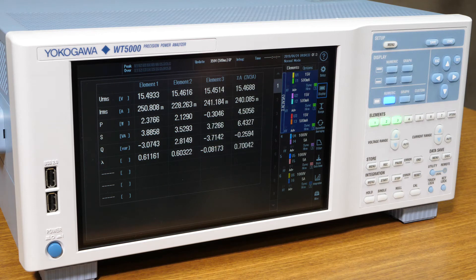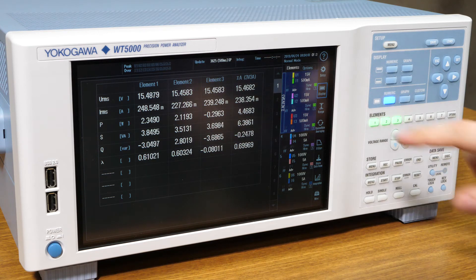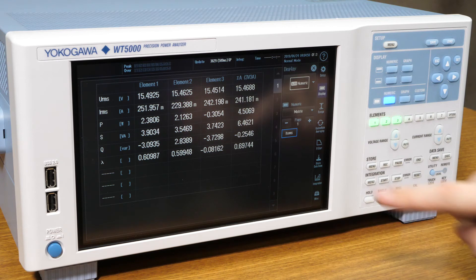Now we are going to walk through setting up the delta computation functions on a WT5000. This process will be very similar on other Yokogawa power analyzers. We will start in the numeric matrix view, but the steps for any of the other views will be similar. First, we will select Display, then select Items.